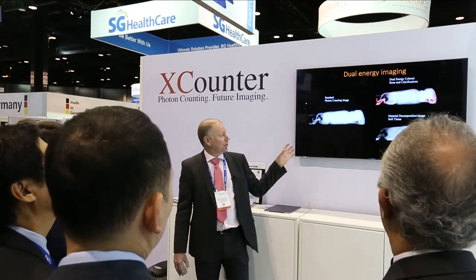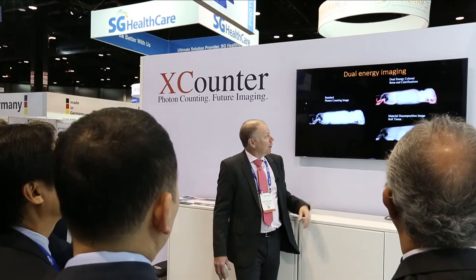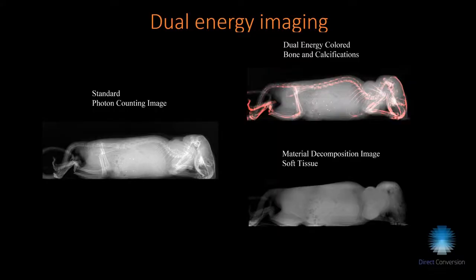For dual energy, we can do material separation. Here is a standard image — photon counting in this case — and in the top version we've highlighted where there is calcium content, and in the bottom right we have removed the bone. This is all acquired from a single shot image; it's the same image with material decomposition algorithms applied.